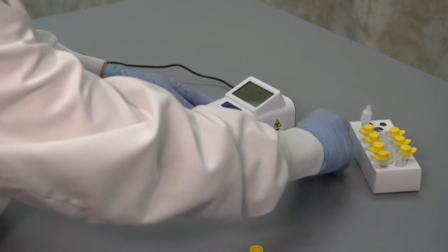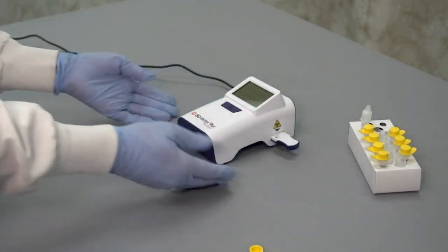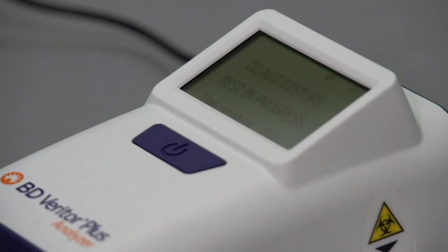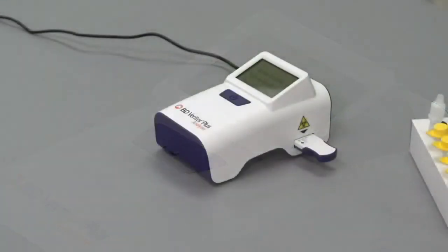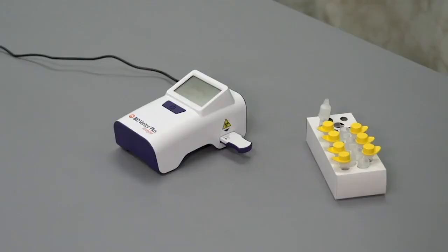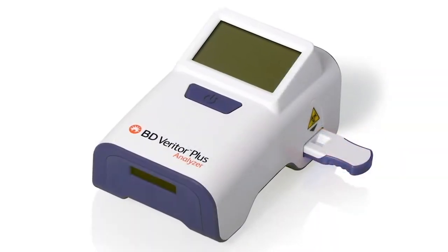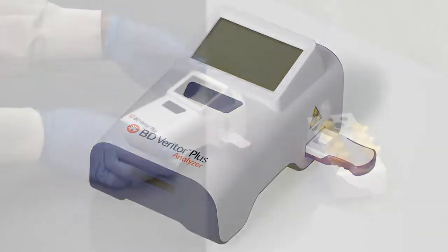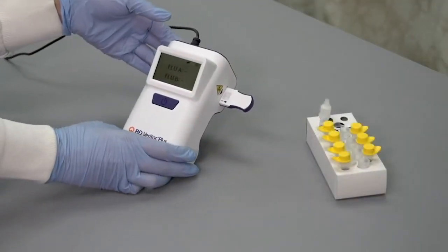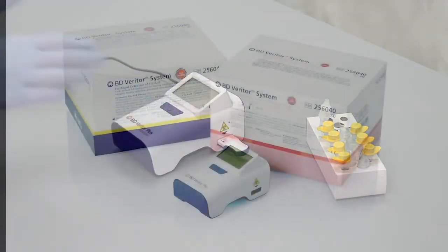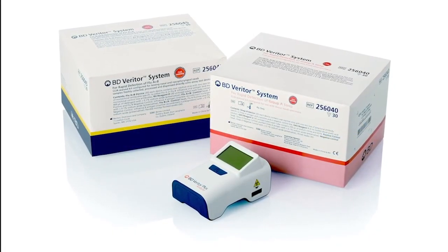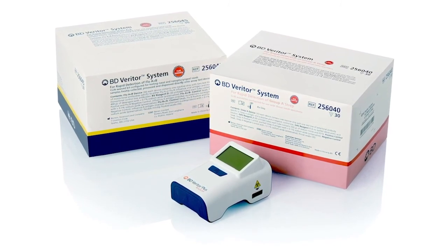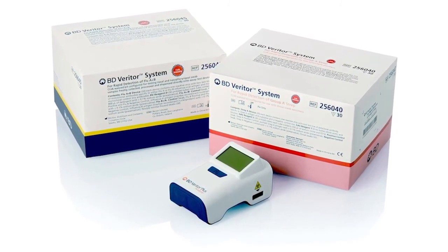A countdown timer appears on the LCD screen indicating the assay incubation period. Depending upon the type of test, the countdown will take from 5 to 10 minutes. After completion of the countdown, test results are read, analyzed, and displayed in a few seconds. The test result remains on the display screen as long as the test device is in the instrument or until the auto-off period is reached, either 15 minutes on battery power or 1 hour with the power adapter plugged in. Make sure to record the test result before removing the test device.